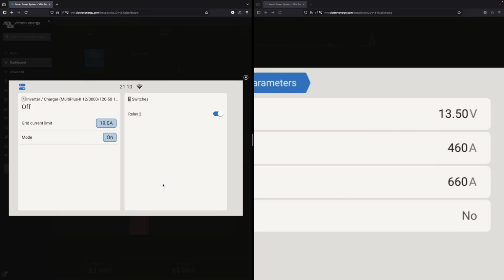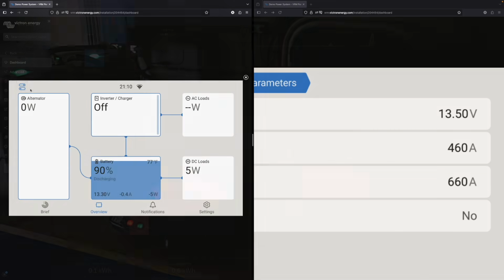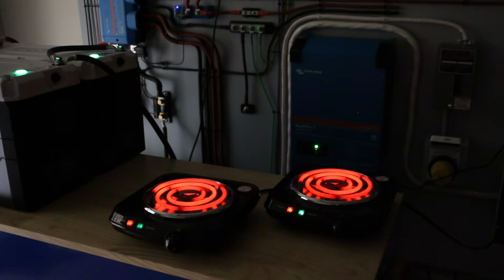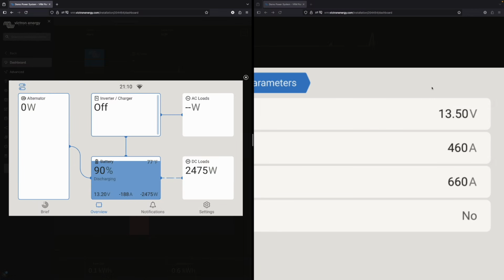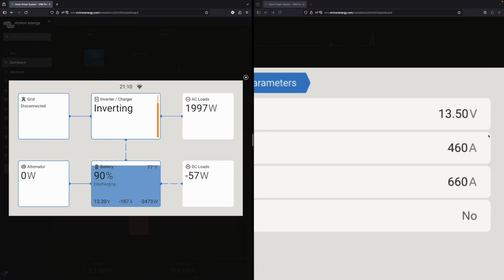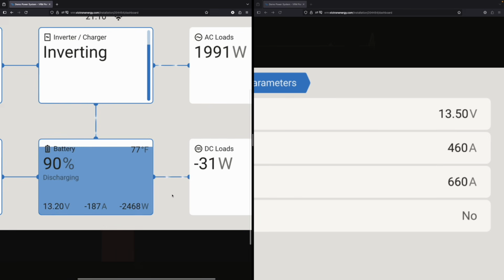I've disconnected the power grid, so it's going to run some loads — we've got some electric stoves — and it's going to run the batteries down to 89%. Watch this number here: when it hits 89%, our charge voltage limit is going to go back up to 14.2, because the batteries are run down enough to allow a new absorption cycle. We'll give it just a second here — it's going to hit 89% on the battery, and then the charge voltage limit should go back up.